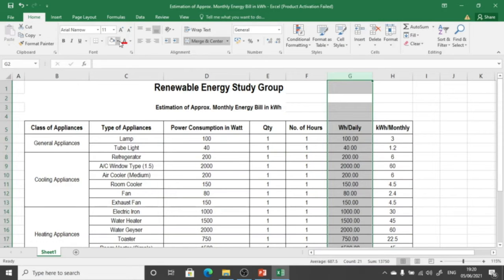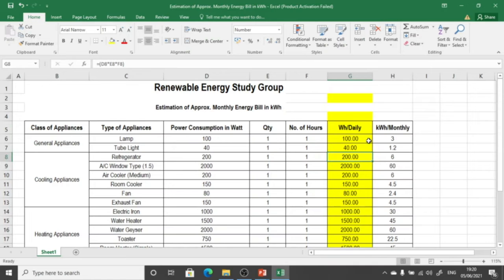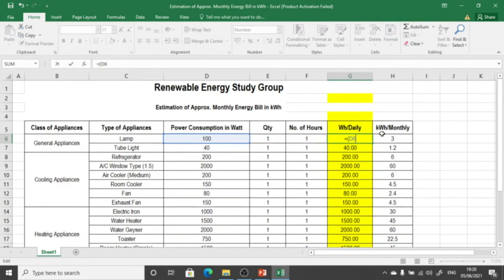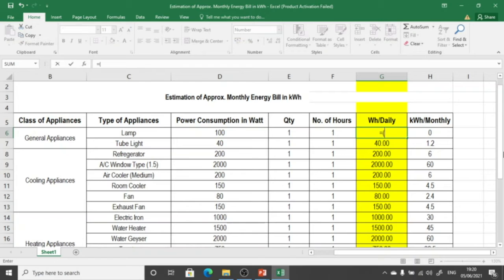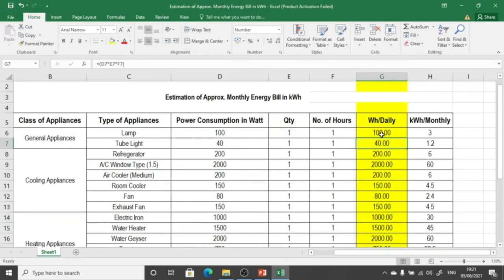The sixth column is watt-hour per day — how much watt-hour each appliance consumes on a daily basis. To calculate daily watt-hour, we select the power consumption cell of the appliance, multiply by the quantity, and multiply by the number of hours it is working. For example, taking a lamp at 100 watts, multiplied by quantity, multiplied by hours of operation — press enter and it shows the watt-hour consumption for that lamp.